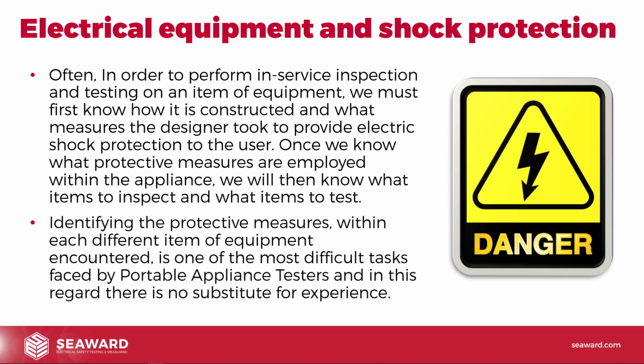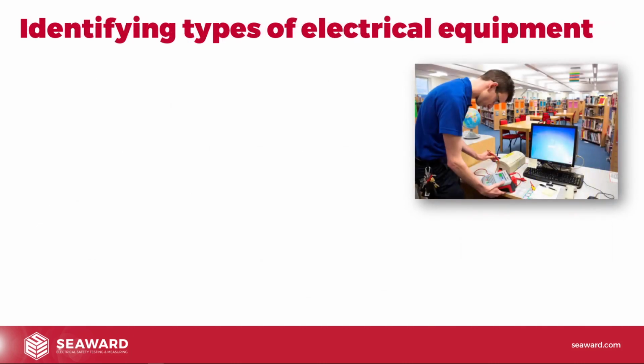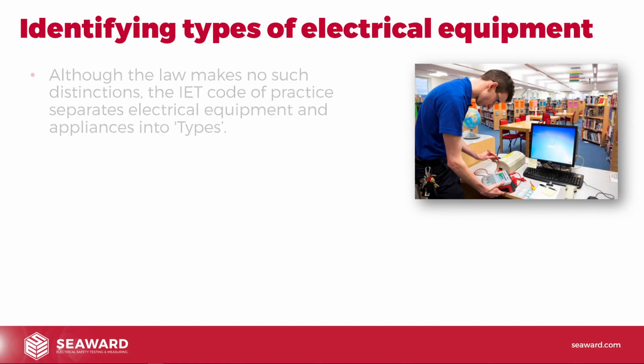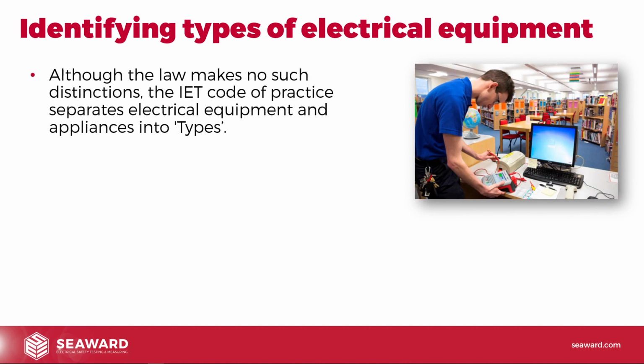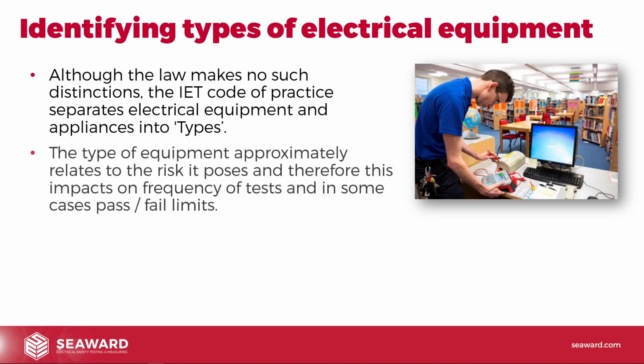Identifying the protective measures within each different item of equipment encountered is one of the most difficult tasks faced by portable appliance testers. And in this regard, there is no substitute for experience. Identifying types of electrical equipment. Although the law makes no distinction, the IET Code of Practice separates electrical equipment into types. The types of equipment approximately relate to the risk posed and therefore impact on the frequency of tests and in some cases the pass-fail limits.